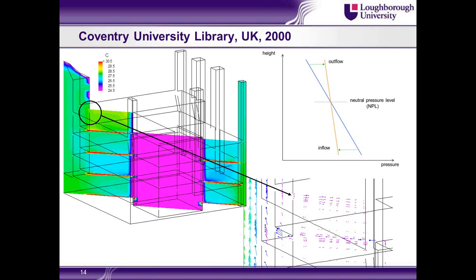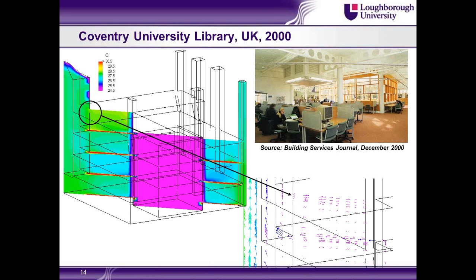So in this design, because there wasn't enough height above the roof here, because of the height restrictions for this building, the neutral pressure level had dropped to somewhere in this region here, so that there was backflow onto the top floor. This was solved by sealing the top floor from the central light well and adding a dedicated exhaust stack to that floor. So it was nice for me, after having done the computer simulations to identify this problem, to actually have an impact on the design and construction of the building in that way.